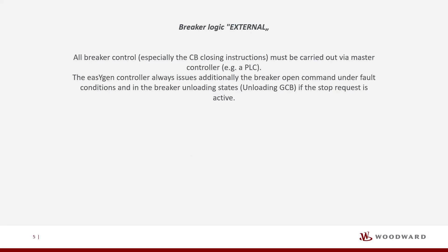Breaker logic external: all breaker control, especially the CB closing instructions, must be carried out via master controller, for example a PLC. The EasyGen controller always additionally issues the breaker open command under fault conditions and in the breaker unloading states, unloading GCB, if the stop request is active.